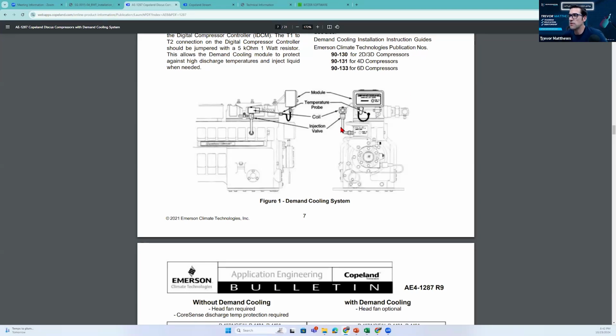I've seen these bend before quite easily. You have to have a full column of liquid. I think in the Copeland manual, they say 5 degrees subcooling, 2 or 3K subcooling coming in. Maybe that's the liquid injection. No, that's the DTC valve, not for these ones. But either way, you got to have a full column of liquid going into them.